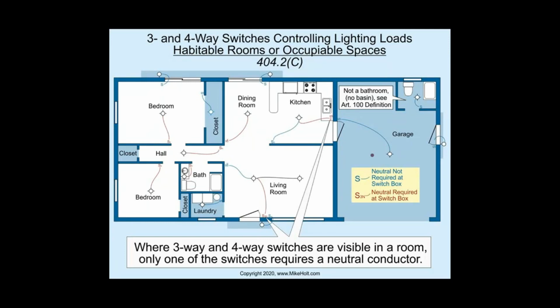This kitchen receptacle is interesting because there's the exception. If both switches are visible one from another, you do not need a neutral at both boxes. Now, if this switch was on the other side of the wall in this kitchen, this blue one, you would need a neutral at both switches. And that's what they're showing you here with living rooms. The garage is not a habitable space. The bathroom is not a habitable space. The closet is not a habitable space, so you don't need neutrals at those locations either.